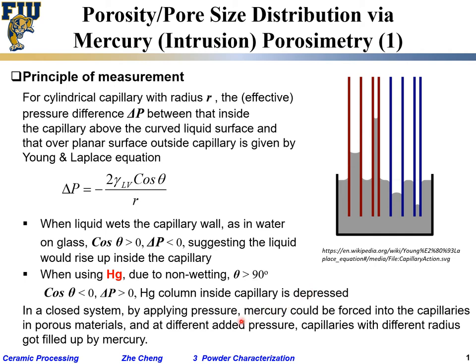In a closed system, by applying pressure we can force the mercury gradually into different sizes of pores or capillaries. For smaller pores, we must apply higher pressure for the mercury to enter. For larger pores, we do not need as much pressure. That is essentially the principle of mercury porosimetry.